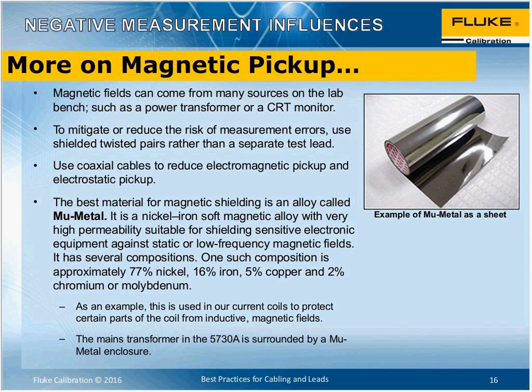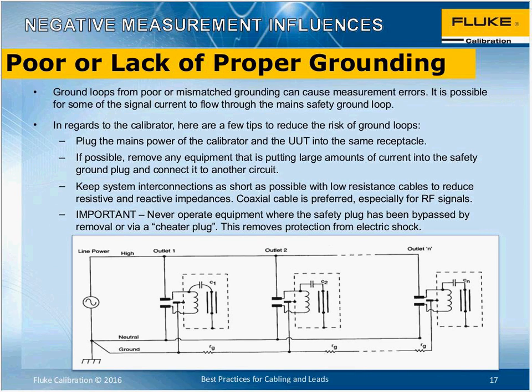Now, about grounding. Grounding is another area where we can get ground loops, and we can get voltages appearing in our measurement circuit when we think they shouldn't be there, because there are often ground currents flowing around where we make our connections. Sometimes those connections are obvious, like we've plugged our line cords into different parts of our electric circuit where the ground potential is slightly different because there are heavy loads running. Something big is plugged in that has a big load, and if there's leakage current running down the ground wire, that can actually cause the ground to move up and down. This is a common effect.